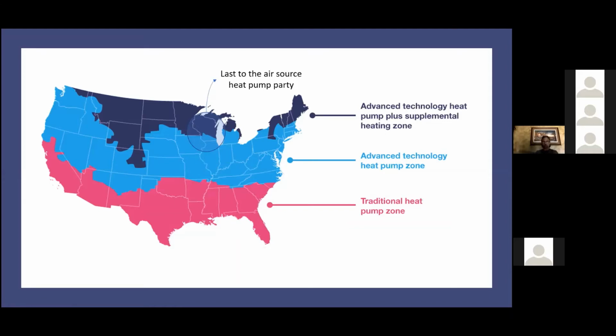Why? Well, because there's moments when it gets kind of cold here in the central strip of the country and the heat pumps can't produce enough heat. So where we are, there are not a lot of heat pump sales because it gets so cold that the heat pumps fall off. We'll talk about why a little bit more when we get to the compressors. Okay, so what we have to do in these advanced technology plus supplemental heating zones is we have to add heat, or we've got to come up with some magic.